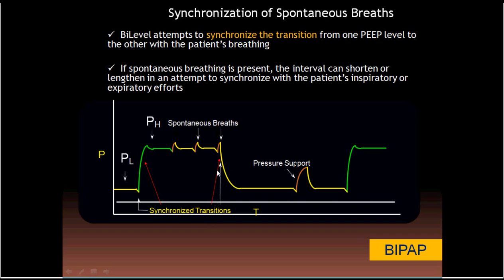They added something else: instead of being a plain mode with just high CPAP and low CPAP, we can add pressure support. This pressure support can be added either to the lower CPAP or to the higher CPAP — it differs from machine to machine. This makes it a little bit more complicated instead of being simply two CPAP levels.